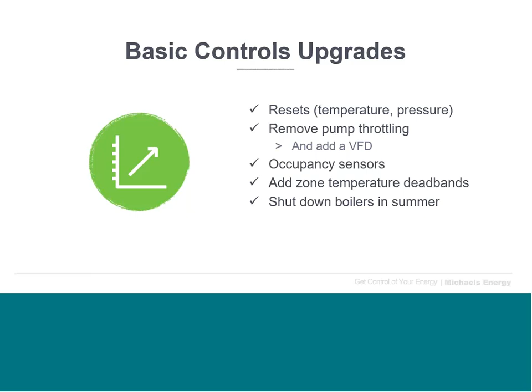So as an example of this, we looked at a hospital that was built in 2013, and it had what's called a variable air volume system, or a VAV system. And that system was set to run at a constant temperature all year round. The reasoning for that was they had a couple of electrical rooms that had a fairly high heat load in them, so they needed cooling year round. Well, we recognized that would end up penalizing them during most of the winter months. So we recommended that they pull those electrical rooms off that VAV system and reset their discharge air temperature. And that reset saved $55,000 a year at a cost of a little over $5,000. So that paid back in just over a month.